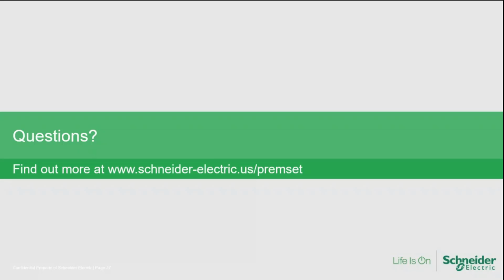How do you compare life expectancy, AIS, GIS, and SIS? I have to explain something a little bit. When manufacturers give out a published life expectancy on switchgear, normally what they're doing is finding a midpoint in the product life cycle bathtub curve that you may remember from an engineering economics class, where we're trying to find the midpoint expected life of a piece of gear. Some will last quite a bit longer than that, and some will fail earlier than that, depending on the environmental ratings and things like that.